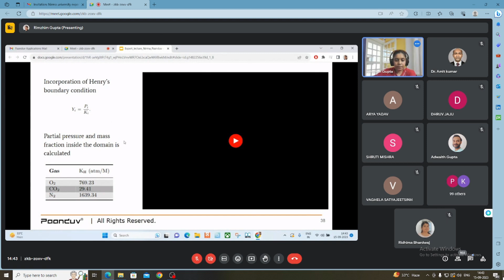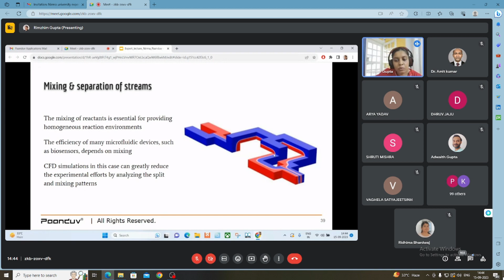Another example of microfluidics is mixing and separation of reagents in a microfluidic channel. This mixing becomes very difficult because these microfluidic channels are dominated by capillary forces rather than gravity forces, so mixing becomes very crucial. Therefore, we apply strategies such as splitting the channel or recombining the channels so that the mixing is optimized. We have used a similar strategy in this particular application.